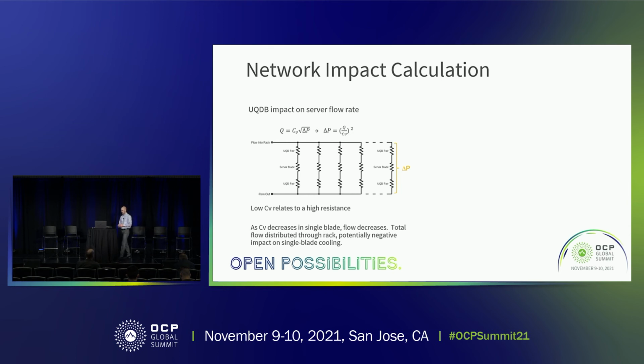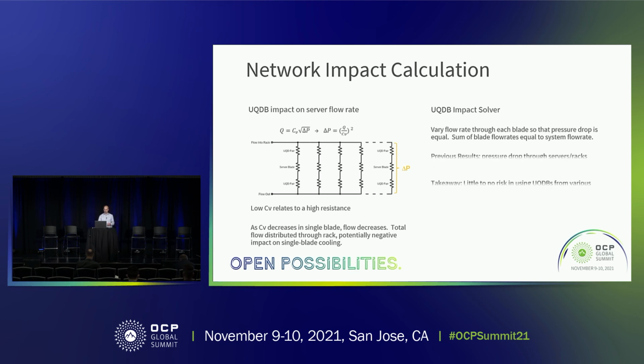What we did is we built a calculator that iteratively solves this kind of idealized problem, matching the system flow rates and the sum of those 8, as well as looking at the pressure drop, where the drop across all is equal, to see what the actual impact on flow is to that last server blade, and then from there, what the actual impact on cooling temperature is. What we found when we performed that calculation is that there really isn't an effect. The pressure drop through the blade is so much higher than the pressure drop across the UQD that any change in that UQD is essentially negligible, and there's no significant impact on the flow through it, or on the temperature, the heat capture.